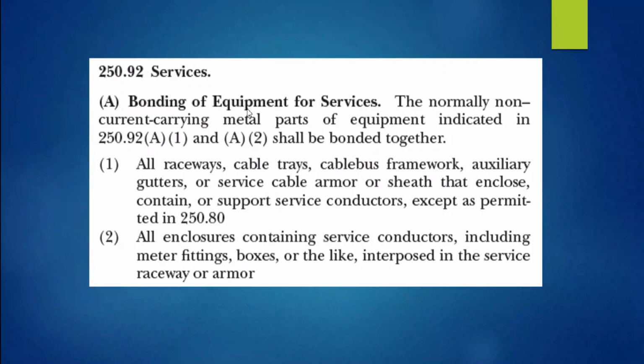250.92(A), bonding of equipment for services. The normally non-current-carrying metal parts of equipment indicated in 250.92(A)(1) and (A)(2) shall be bonded together. That means all raceways, cable trays, cable bus framework, auxiliary gutters, or service cable armor or sheath that encloses, contains, or supports service conductors, except as permitted in 250.80. And that's talking about those metal elbows that might be buried at least 18 inches in the ground. Then there's really no way to bond that elbow.